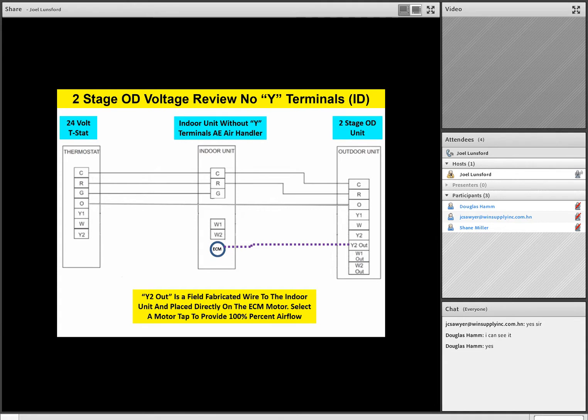So if it's getting a Y1 call, for instance, or a G call at 65% airflow, and in our example, if it sees another speed tap command from our Y2 out for second stage airflow, even though it already has a Y1G command at 65% airflow, if it sees an additional command for a higher airflow setting, it'll drive to the highest airflow setting. So this is an important concept with all ECM motors. If they receive more than one speed command, they always take the highest speed command as priority. Are there any questions or comments on that in this basic low voltage block wiring? If we have, for instance, a two-stage outdoor unit with an AE air handler with no Y terminals at all, or if we have an indoor unit with Y terminals. Any questions or comments on this?